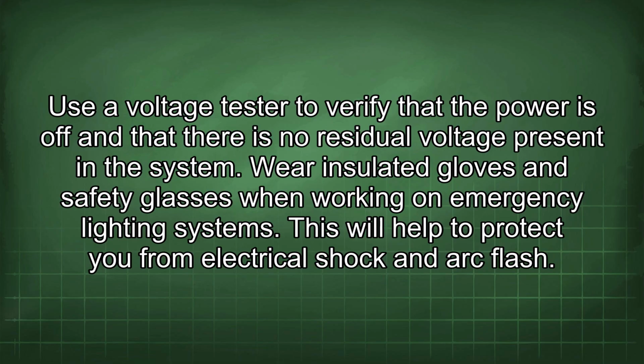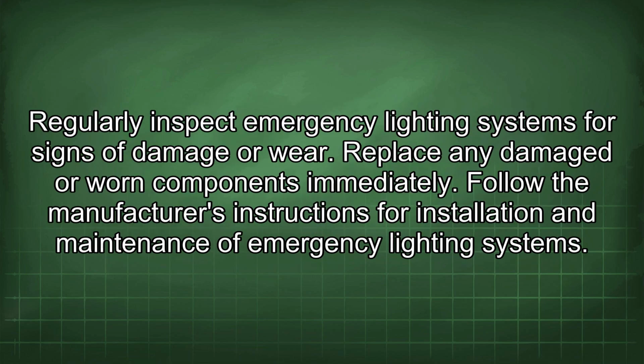Use a voltage tester to verify that the power is off and that there is no residual voltage present in the system. Wear insulated gloves and safety glasses when working on emergency lighting systems. This will help to protect you from electrical shock and arc flash. Regularly inspect emergency lighting systems for signs of damage or wear. Replace any damaged or worn components immediately. Follow the manufacturer's instructions for installation and maintenance of emergency lighting systems.